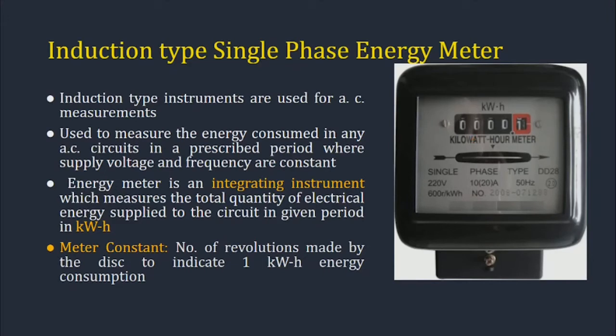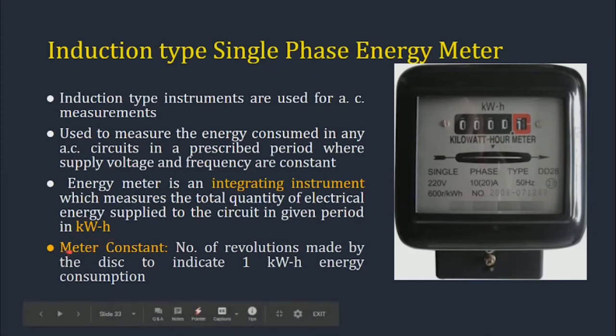Measurement of energy: induction type instruments are used for AC measurements and to measure the energy consumed in AC circuits over a prescribed period where supply voltage and frequency are constant. It is an integrating instrument that measures the total quantity of electrical energy supplied to the circuit in a given period, in kilowatt-hours. The meter constant is the number of revolutions made by the disc to indicate one kilowatt-hour energy consumption.